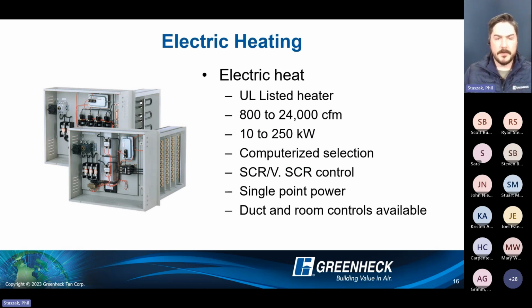So from an electric standpoint, as far as makeup air goes, the RV model, again, as Chris mentioned, if you're looking for more of the heat pump style units. But if you're looking for just general electric heat options, we do offer an MSX model with an electric heater all the way up to 250 kW and roughly 24,000 CFM is what that equals out to be. An advantage from a manufacturing stance when we look at electric heat is it is single point power. Many other manufacturers, because it's high amperage associated with these electric heaters, will offer a secondary power source. So you'll have a breaker required for your electric heater and then a breaker required for the makeup air. As a standard, as a manufacturer, we decided to go with one disconnect sized for the entire unit, making it a lot easier and lower cost for the installation side of it. So your electrician doesn't need to feed two separate supply wires up to the unit.